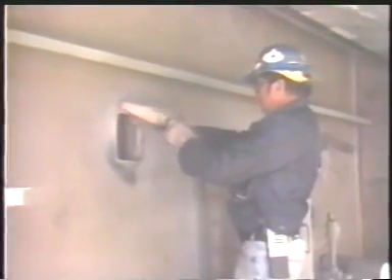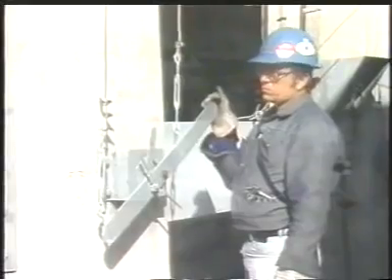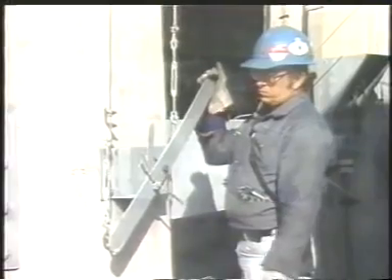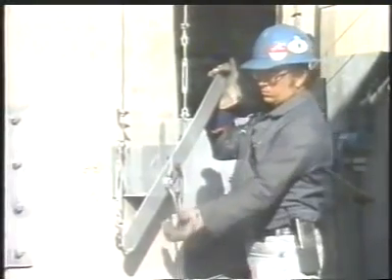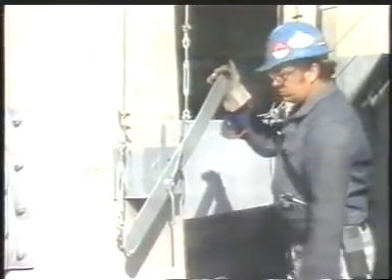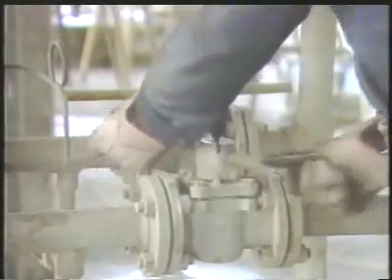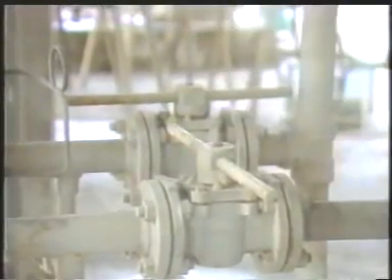When minimum firing has been reached, you shut off fires and open the PEEP doors. Process circulation is continued to cool down the tube slowly. Next, you open the stack damper and air registers to purge the furnace. Then block the fuel systems, including the burner and regulator valves.